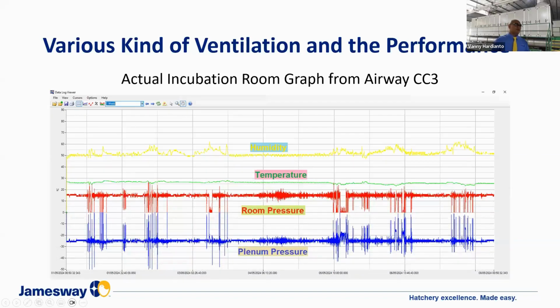Our ventilation system also has a recording system. It will record all data like temperature, humidity, pressure, or even the fan speed or the pump speed. So we can trace back when we have an issue with our performance. Here is the sample data: the yellow color is the humidity, and the green color is temperature. Red color is the room pressure, and the blue one is plenum pressure.